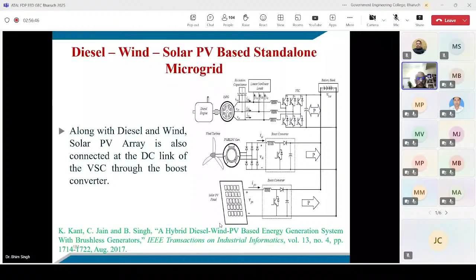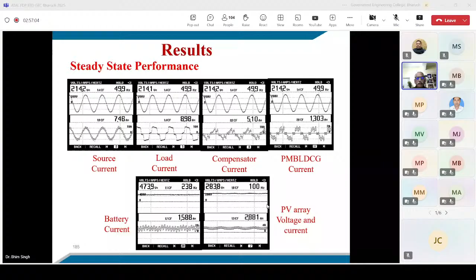This non-linear load is fed from this setup, but the source current THD was quite low, typically 4.9%, while the THD of voltage was only 1.1%. So this synchronous generator was not saturated. When a machine is saturated, it also has a little distortion in the voltage.